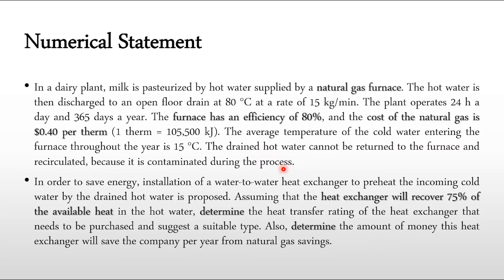The drained hot water cannot be reused in the furnace because it is contaminated, but we can preheat the cold water using that hot water. To save energy, installation of a water-to-water heat exchanger for preheating the incoming cold water by the drained hot water is proposed, assuming the heat exchanger recovers 75% of the energy currently wasting. We need to determine the heat transfer rating of the heat exchanger to be purchased, suggest a suitable type, and determine the money saved per year from natural gas savings.